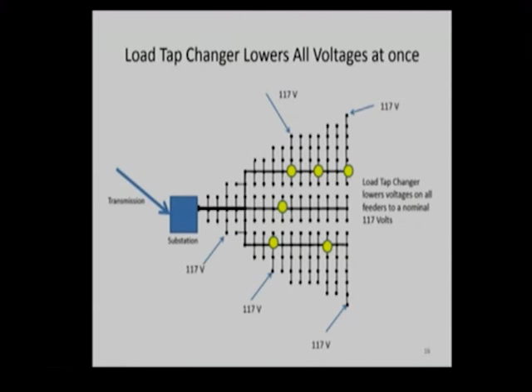So the load tap changer lowers all of the voltages at once, and now I'm showing that you now have a grid where all of the voltages are down in the lower levels, say at 117 volts, with some ability to survive a little power swings with loads changing. But then why stop there, or why not stop there?